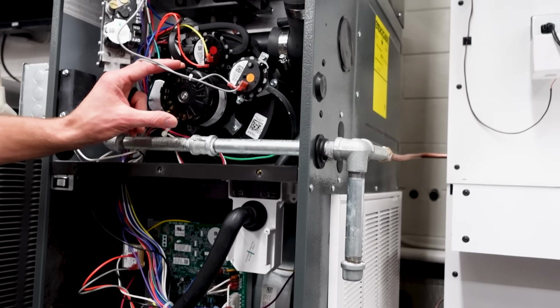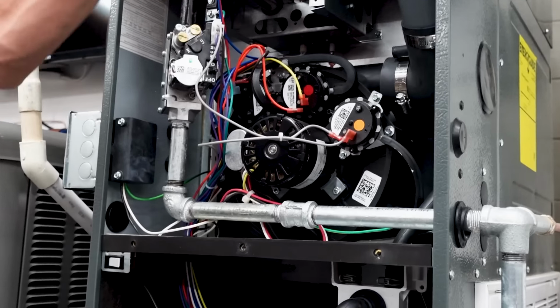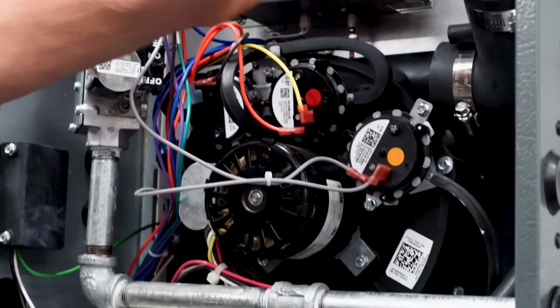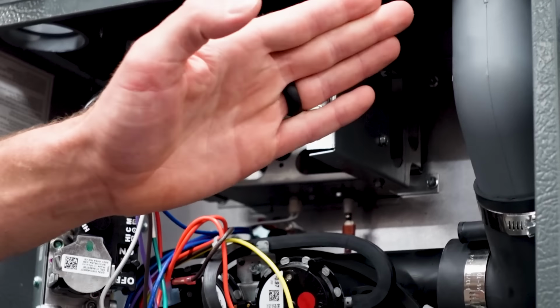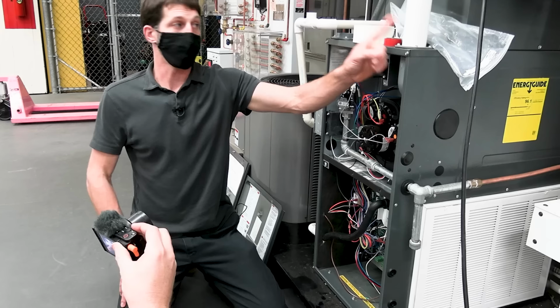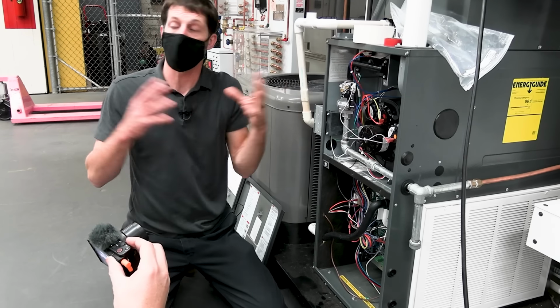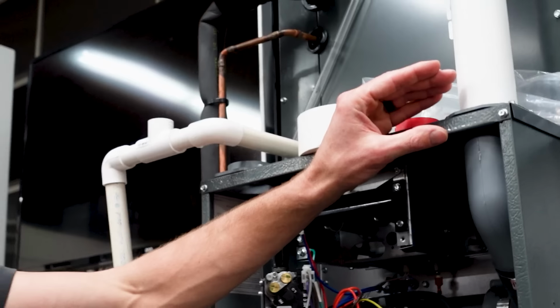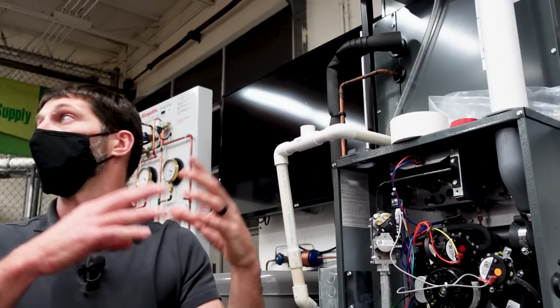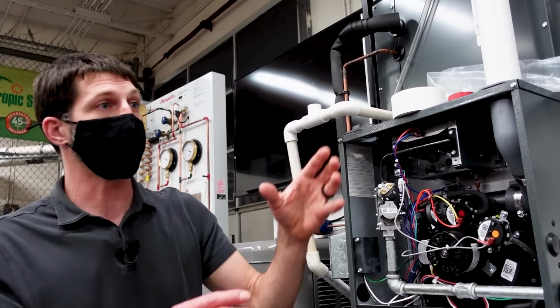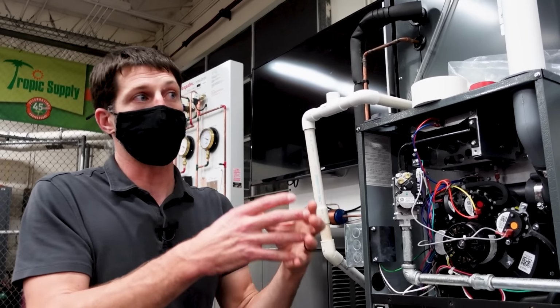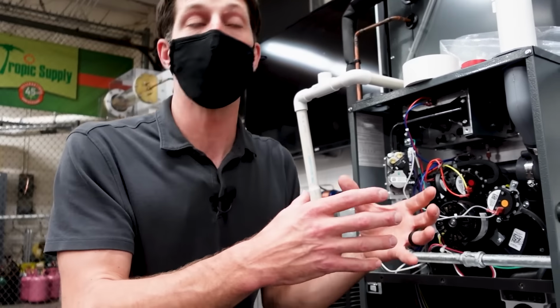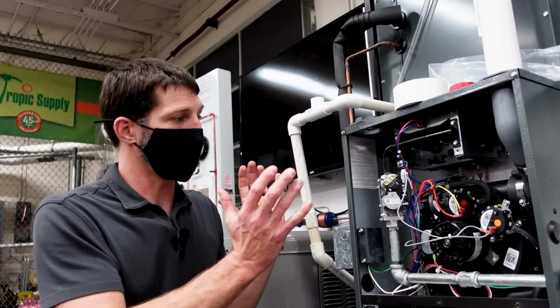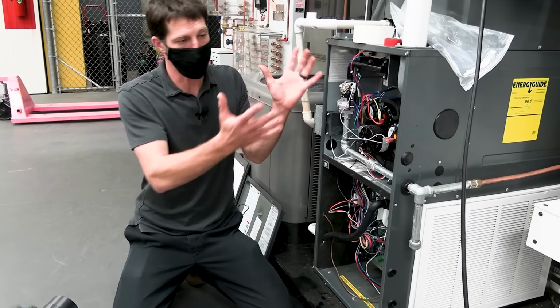This inducer motor, its job is to push the exhaust out through, and anytime you're walking up to a furnace, you know immediately it's 90% or higher if it has a PVC exhaust. This PVC exhaust is basically the temperature of your skin. It can be 0 inches to combustibles where it exits the building, whereas if it's metal and it's a B vent, it's normally around 1 inch to combustibles, such as wood, but you have to look at the ratings for that particular furnace, the temperature of the exhaust traveling through it.